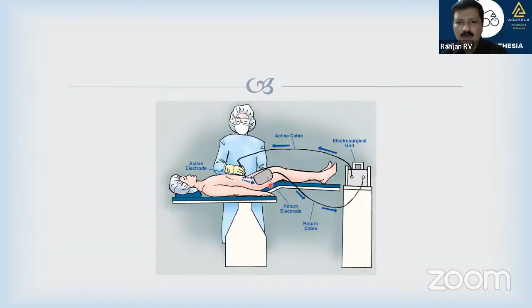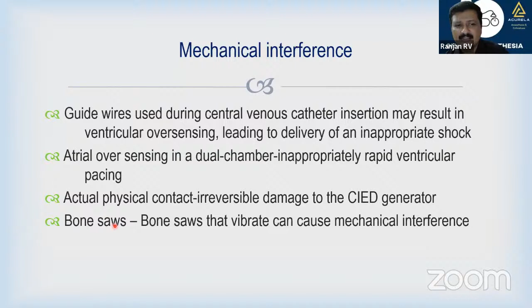Mechanical interference, apart from EMI, even mechanical interference can cause problems. That is your CVP guide wire, it can mechanically dislodge the lead or itself can stimulate the atrium and ventricle, which is dangerous to the patient. Atrial oversensing because of your guide wire can also inappropriately increase the ventricular pacing. Even bone saws, whenever in an orthopedic procedure, whether they are doing a THR, TKR or humerus plating, this bone saw can also cause a problem, mechanical interference.